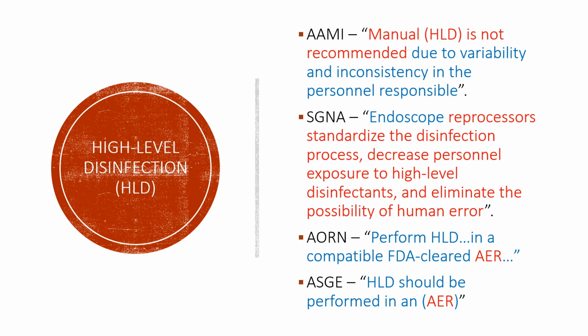AORN, AAMI, and SGNA direct that scopes should not be left in AERs for extended periods, with AORN and AAMI pointedly stating more than 1 hour would require a repeat HLD cycle. AER basins are wet environments, and the intent here is to limit the chance of waterborne contamination.